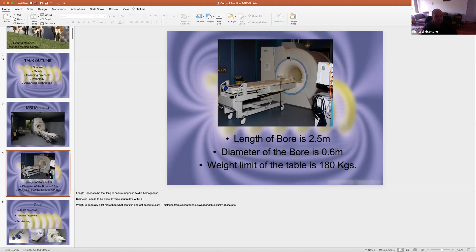There's another picture. We've also got a table. We've got the bottom of that head coil, and we've got the bore of the magnet. The length of the bore is 2.5 meters, so it's 2.5 meters deep. The diameter of the bore is 0.6 meters. This is an older machine. Some of them go up to 0.7, and there's one type that goes up to 0.8 of a meter wide. This means that the machines can be very claustrophobic, so we have to be careful. There are some patients that just can't have the scan because it's too claustrophobic, and we have to give them sedation and things.